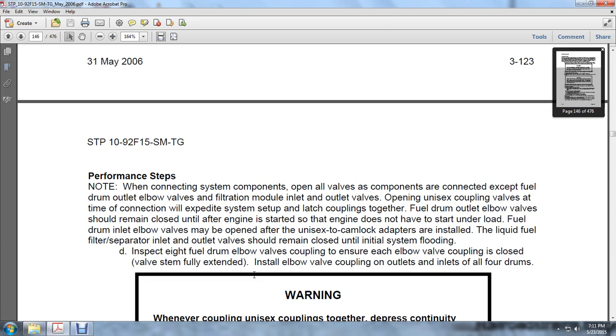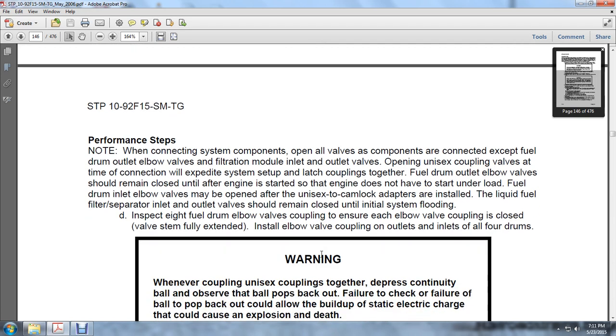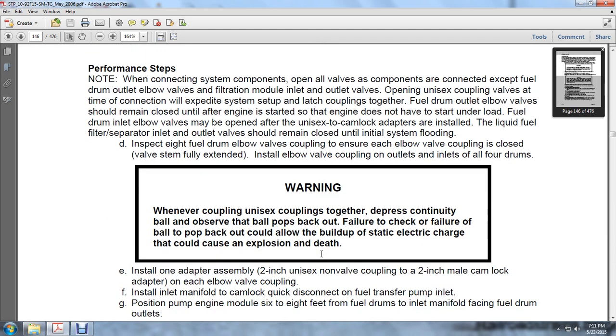Inspect the 8 fuel drum elbow valve couplings to ensure each elbow valve coupling is closed, with the valve stem fully extended. Install the elbow valve coupling on the outlets and inlets for all 4 drums. Whenever connecting a unisex coupling together, depress the continuity ball and observe the ball pops back out. Failure to check and failure to see the ball pop back out could allow the buildup of a static electrical charge that could cause an explosion and death. Install one adapter assembly, 2-inch unisex non-valve coupling, and 2-inch male cam lock adapters on each elbow valve and coupling. Install the inlet manifold cam lock quick disconnect on the fuel transfer pump inlet.